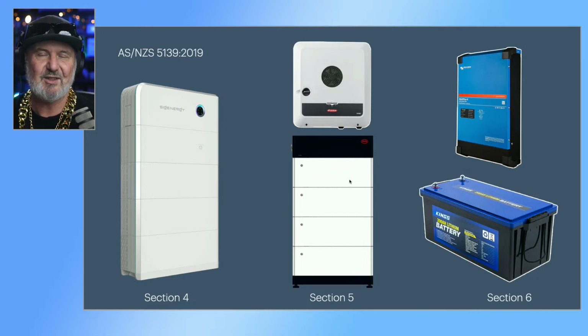So I better explain what these sections relate to. 5139 is really addressing 3 different types of energy storage systems. Section 4 is for a pre-assembled integrated BESS. That means the inverter, or the PCE to be more technical, and the battery system are one product. They can actually be separate, not physically within the same enclosure, but there must be no on-site manufacture of parts. Additionally, they need to meet what's called the best practice guide.